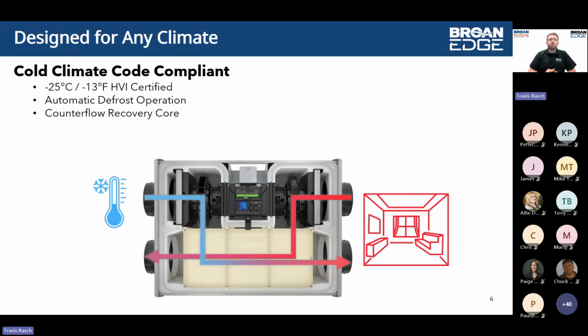With those cold climates, do know that the product has an automatic defrost operation, so no external intervention is required. The unit is monitoring those incoming outdoor air conditions and making the right decisions to properly defrost the product, so that we don't have damage or any other undesired condition happen in those cold climate applications.